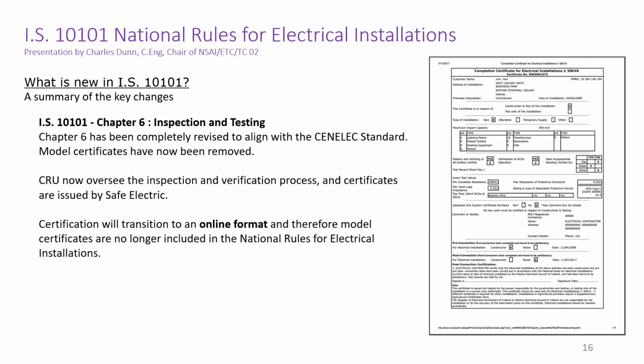Chapter 6, Inspection and Testing, has undergone a big change. Inspection and testing has been completely revised to align with the CENELEC standard. Model certificates have now been removed entirely from the national rules for electrical installations, and there are several reasons for this. The regulator CRU now oversees the inspection and verification process, and inspection and testing certificates are now issued by the Inspectorate Safe Electric and not by the standards authority NSAI.